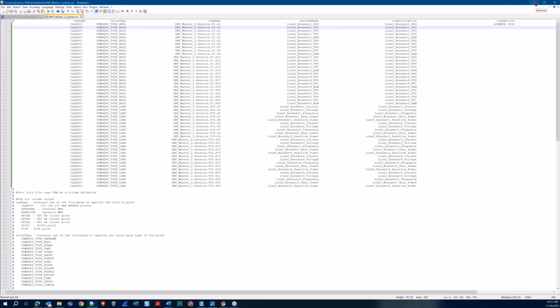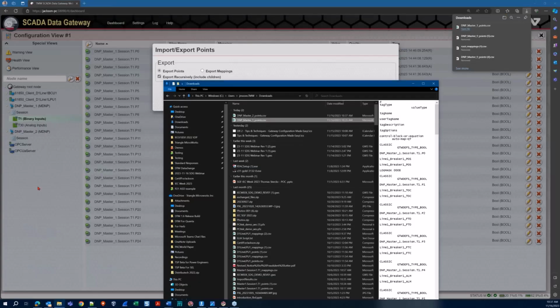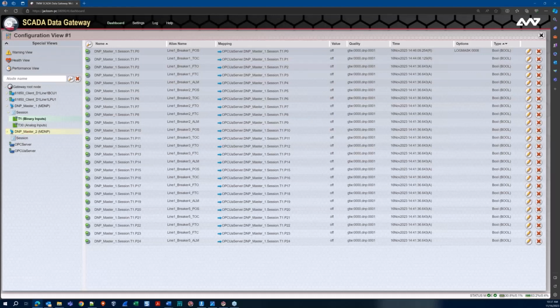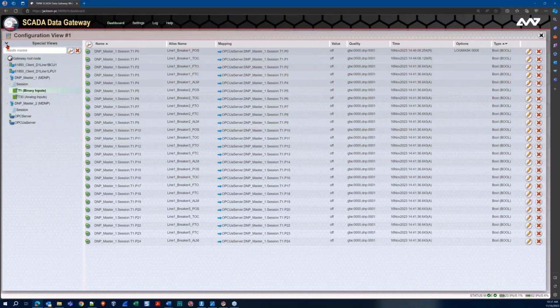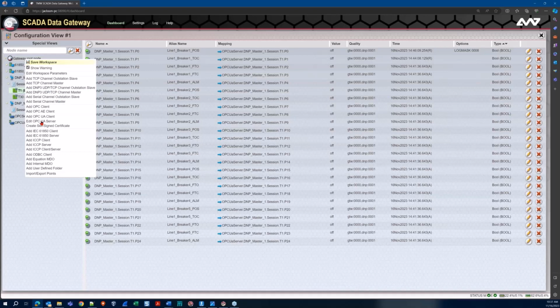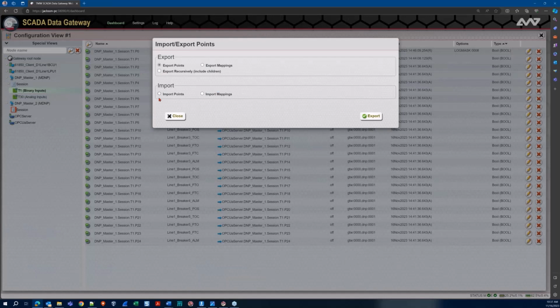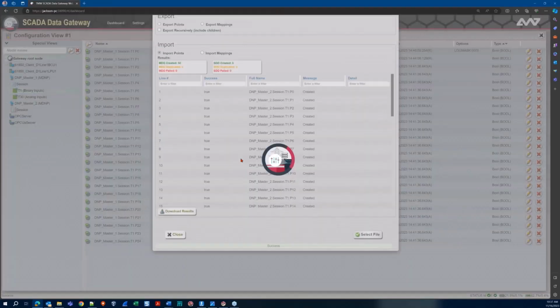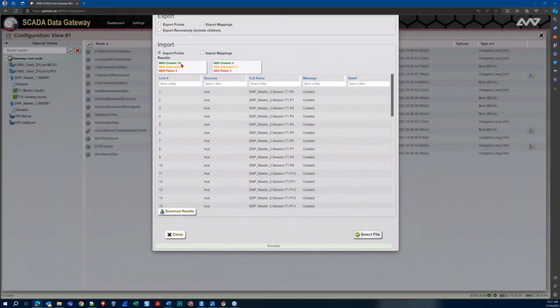And now I am ready to upload this back into my gateway and apply these points that I've just edited to my DNP Master 2 device that I created. In order to do that, I just right click on my gateway root node, and I want to select the import export points option. I click that, make sure that I select import points. I'm not exporting anymore. And then I just need to select my file. Find that file that I just created, DNP Master Points 2, which is a modified version of 1. Just hit OK. And sure enough, I see that it has created 50 points for me.